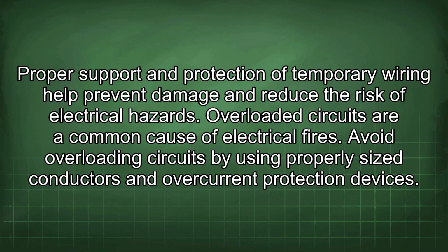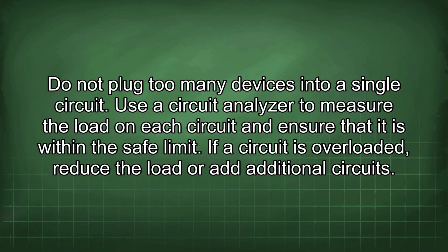Overloaded circuits are a common cause of electrical fires. Avoid overloading circuits by using properly sized conductors and overcurrent protection devices. Do not plug too many devices into a single circuit. Use a circuit analyzer to measure the load on each circuit and ensure that it is within the safe limit. If a circuit is overloaded, reduce the load or add additional circuits.